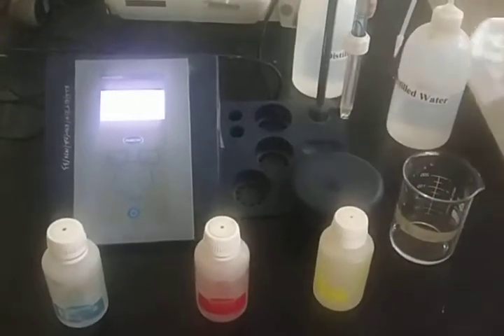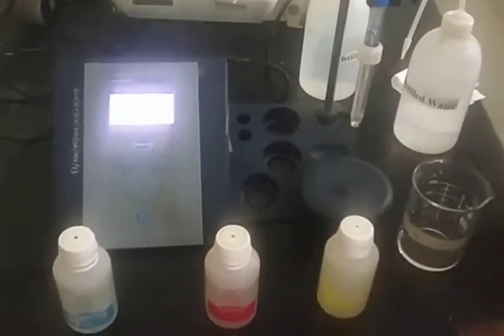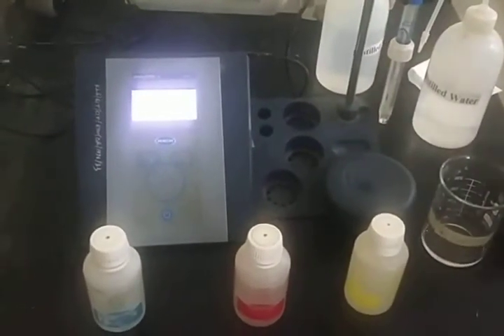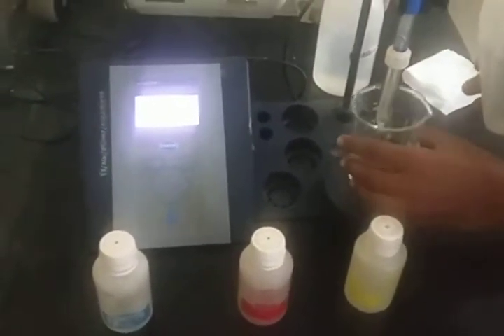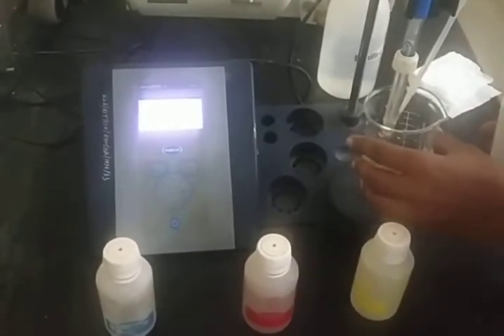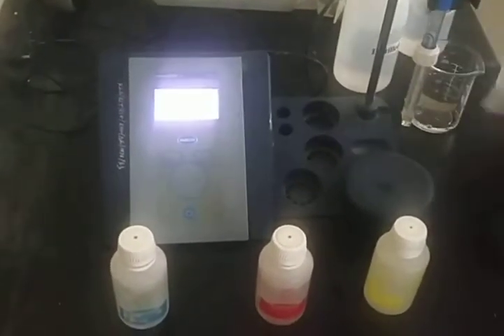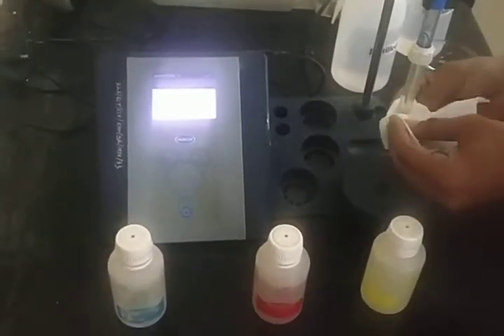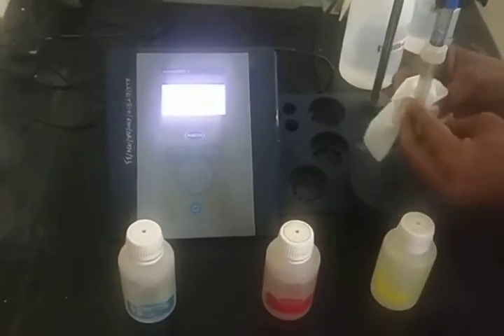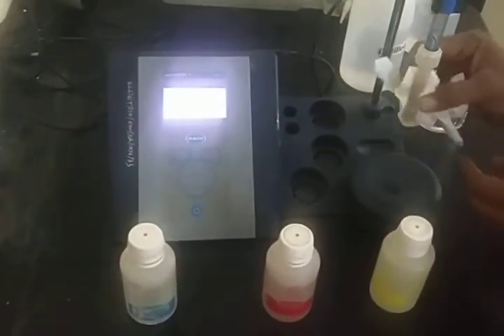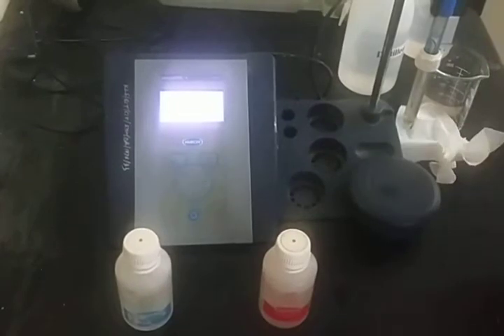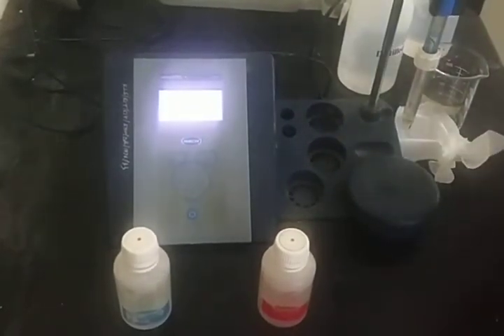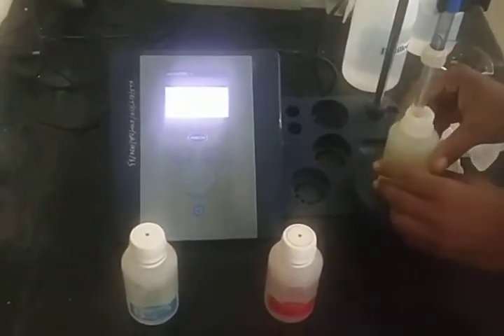Now we'll consider 3-point calibration stepwise. We'll go for 3-point calibration of the pH meter, wherein we are going to calibrate the instrument using 3 buffer solutions. The first buffer solution is going to have a pH value of 7. The second buffer solution is going to have a pH value of 4. And the third buffer solution is going to have a pH value of 9.2.